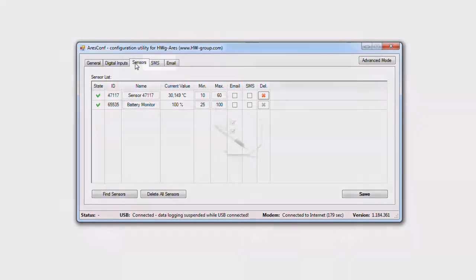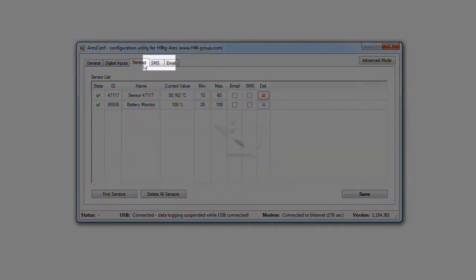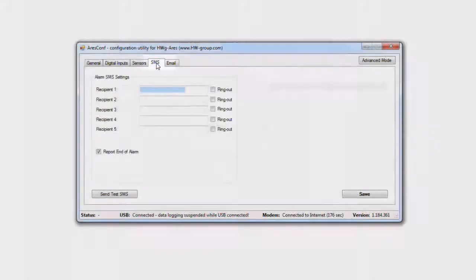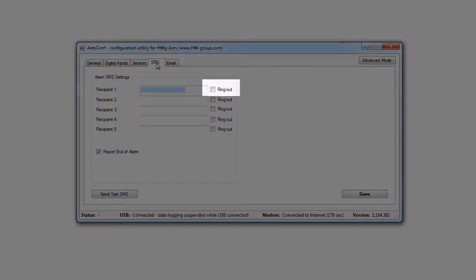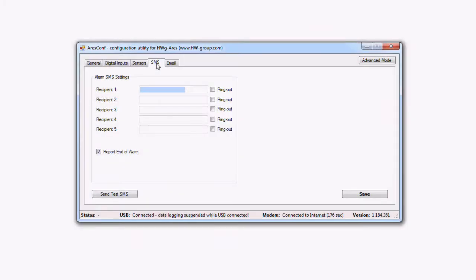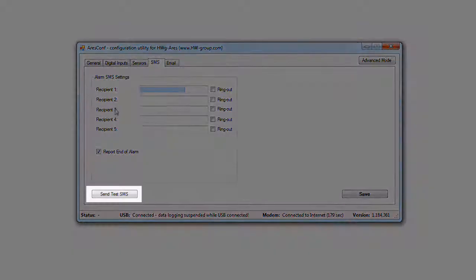In the SMS tab, it's possible to insert phone numbers for sending alarm SMS. At the same time you can set if this phone number will be drop called. It means that the start and end of alarm will be reported by a drop call lasting 15 seconds. You can verify the function by pushing the send test SMS button.